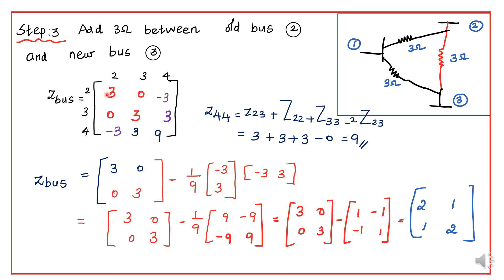How to find the new Z-bus 2x2 matrix? Write the 2x2 matrix: 3, 0; 0, 3. Multiply minus 1 divided by Z(4,4) = 9. Take the column elements: minus 3 and 3. Write the row elements: minus 3 and 3. Multiply: 9, minus 9; minus 9, 9. Multiplied by 1/9: 1, minus 1; minus 1, 1. Subtracting: 3 minus 1 = 2; 0 minus minus 1 = 1; 0 minus minus 1 = 1; 3 minus 1 = 2. So this is the final Z-bus matrix.